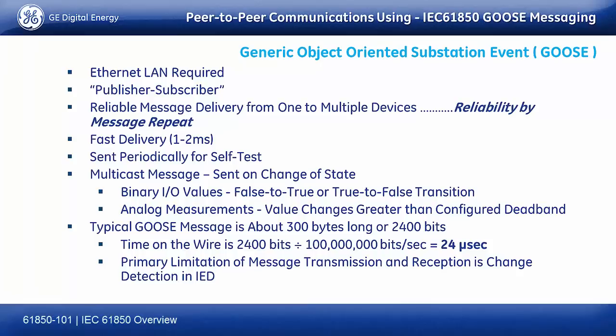So I can publish this quickly and accurately, and it's great for right-now data like protection operations data, tripping and blocking, and so on, because I'm going to send it. I'm not going to wait for an acknowledgement to make sure it's there. I'm just going to send it.